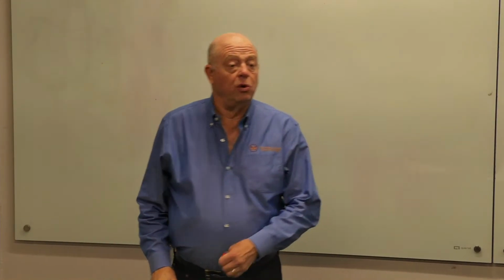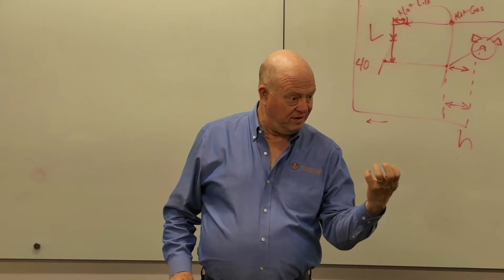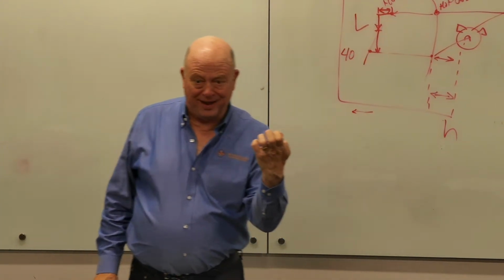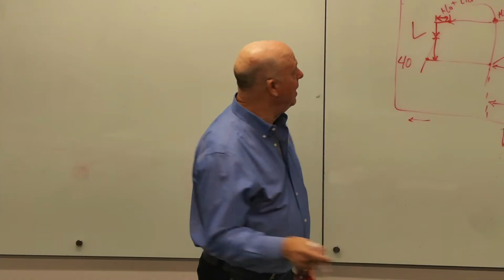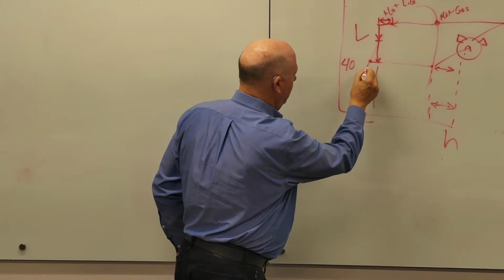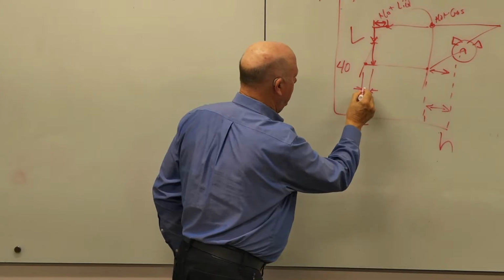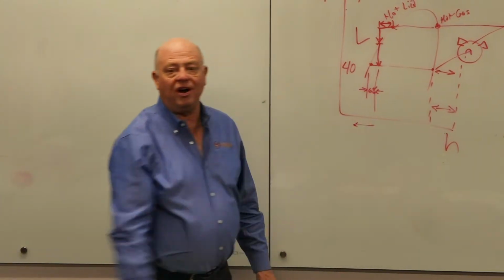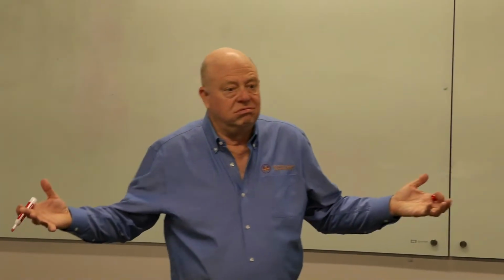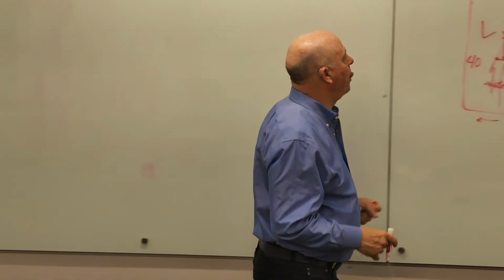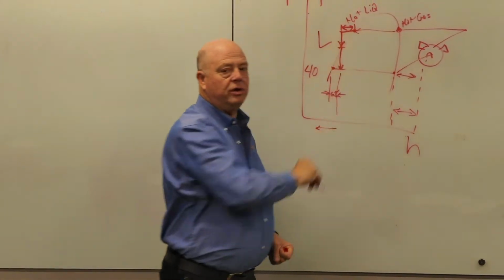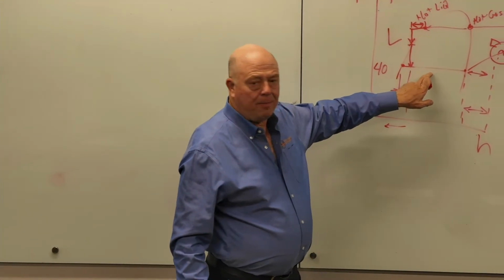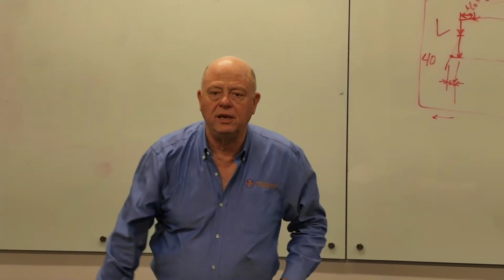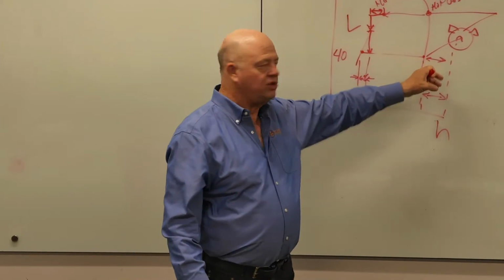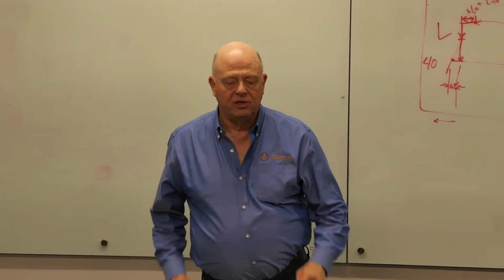Now, just throwing out a number, if for this refrigerant, 94% liquid, 6% gave up its life as a liquid and became a gas so that 94% could be cool, if that was the case, 94 and 6, then this right here would be 6% of the distance across. It's all very simple. Okay? And now we've completed the circuit. And now we've got an evaporator that's got some heat load hitting it, and the stuff's changing state, and eventually it continues to change state.